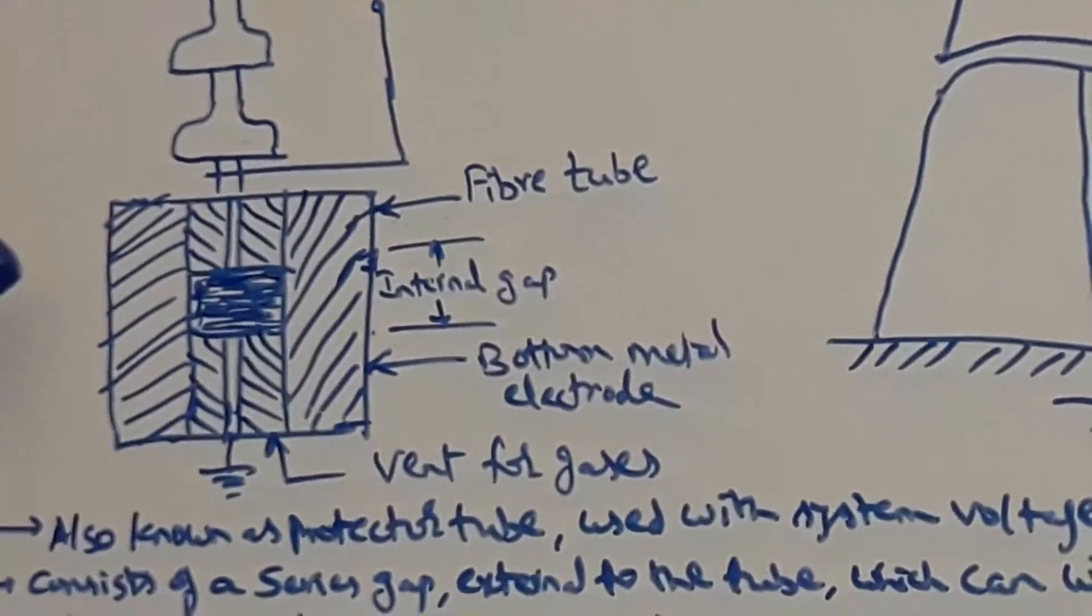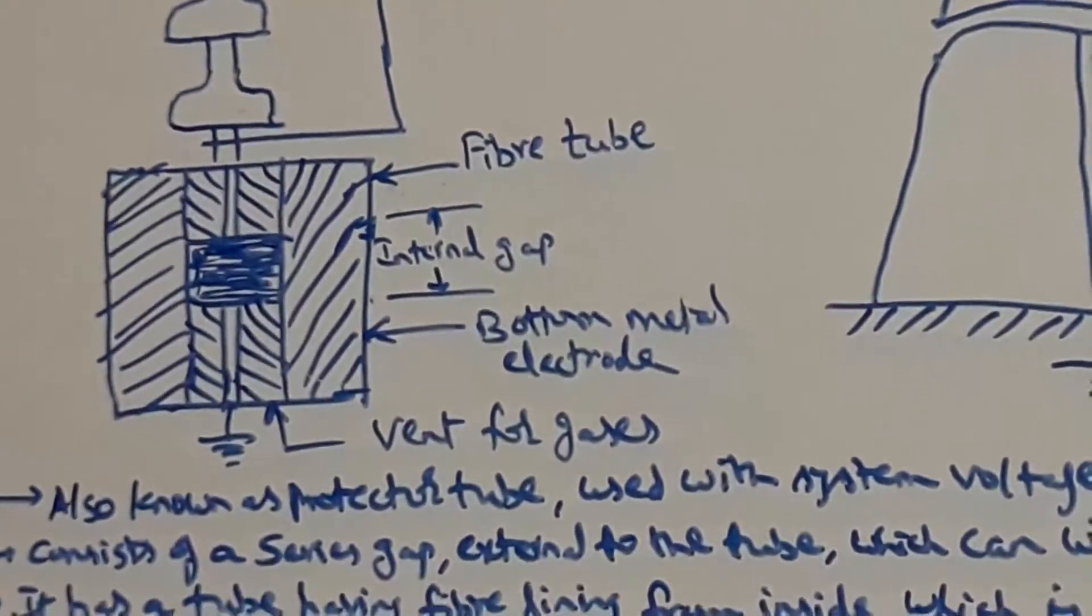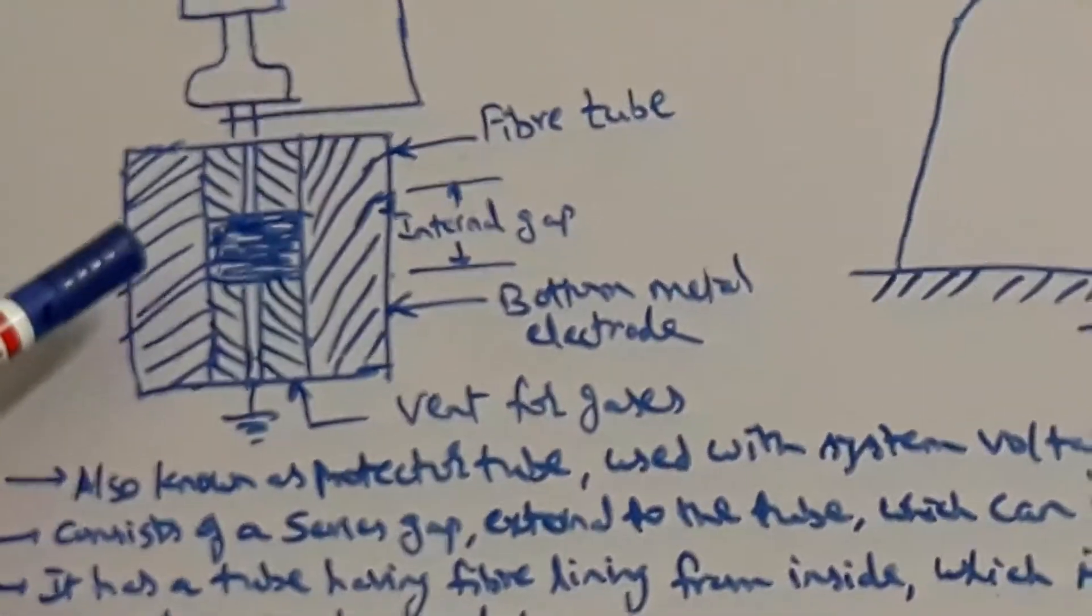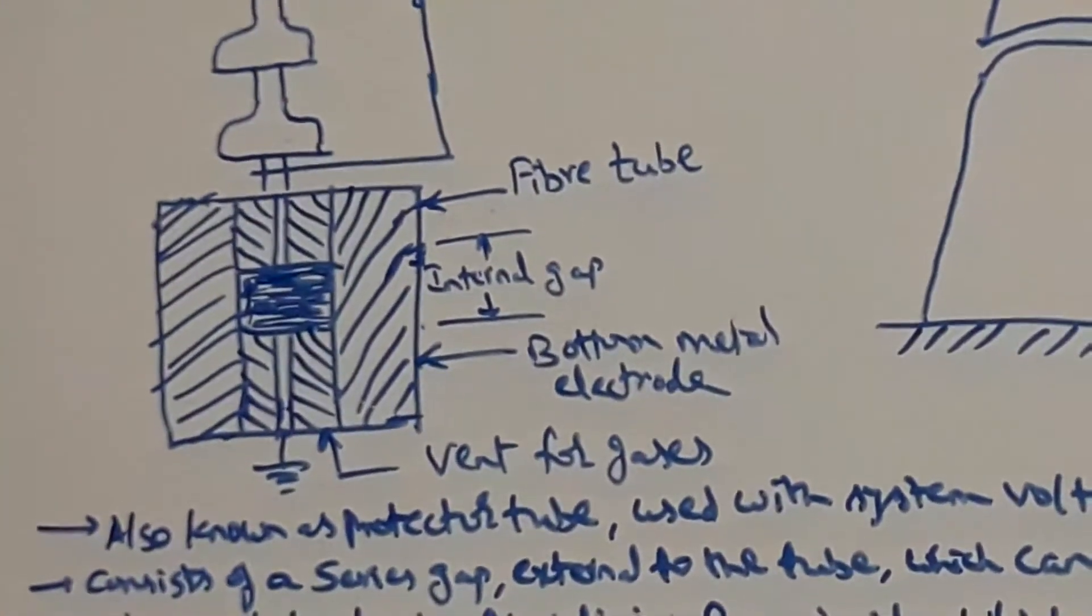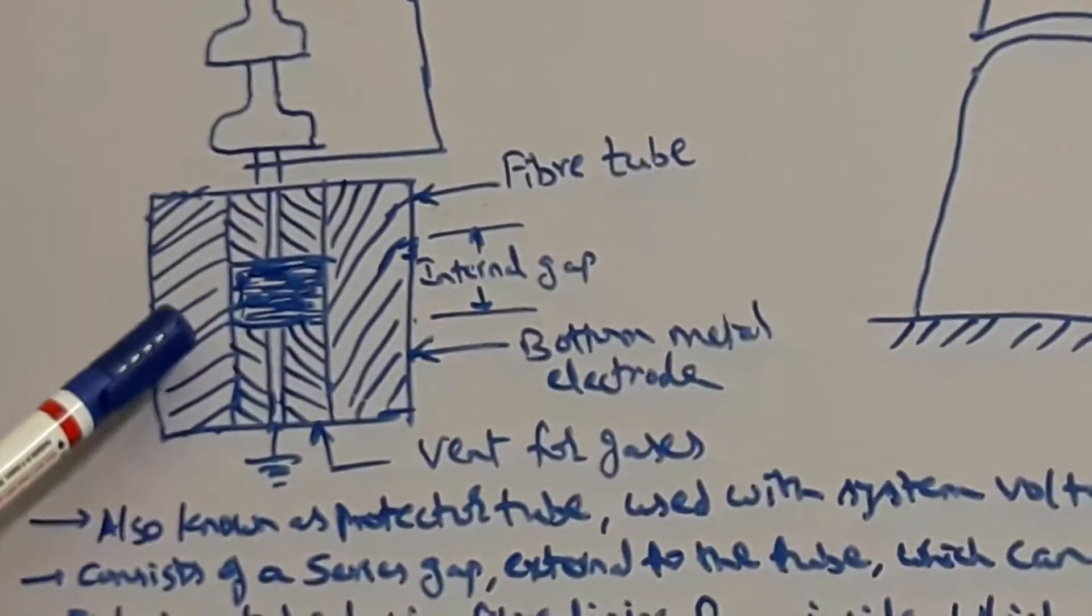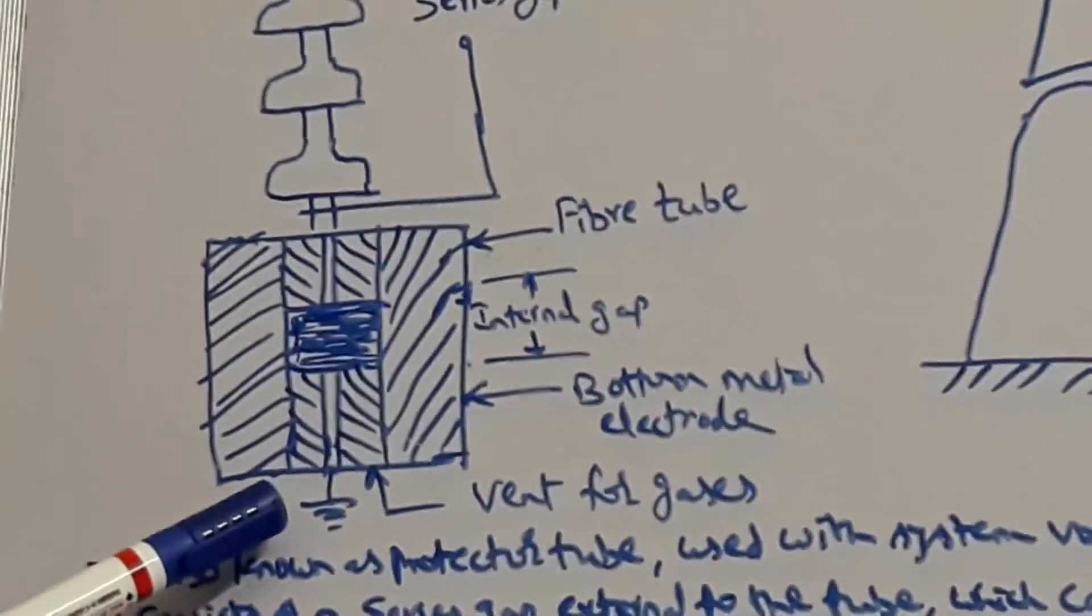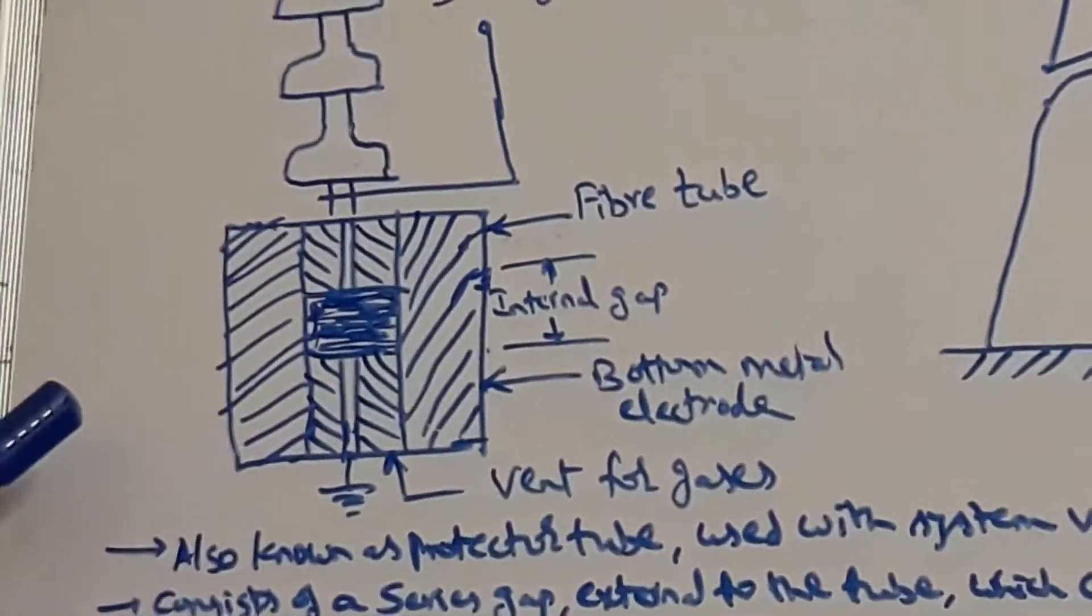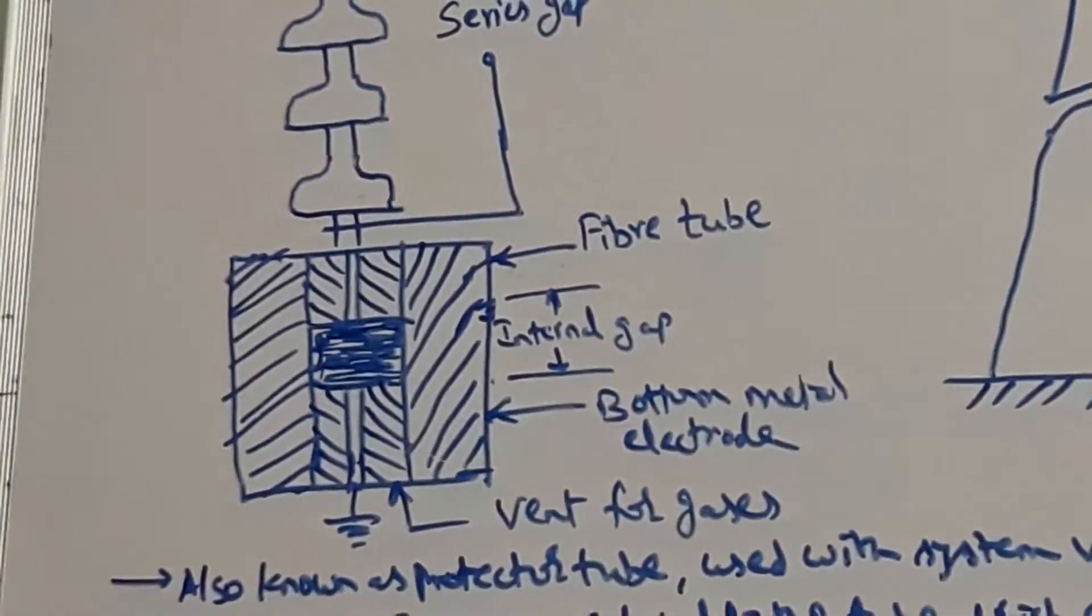The arc vaporizes some of the organic material in the fiber tube, building up high pressure in a short time. This high-pressure gas is expelled out through the bottom vent shown in the figure, after producing turbulence in the internal gap of the tube.